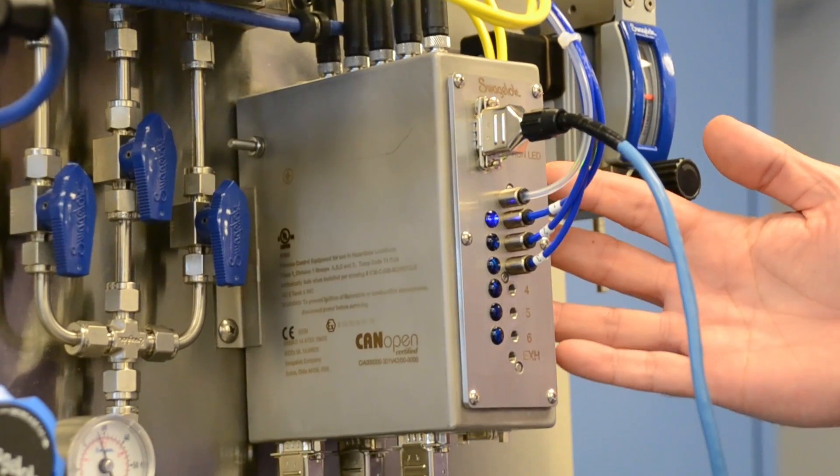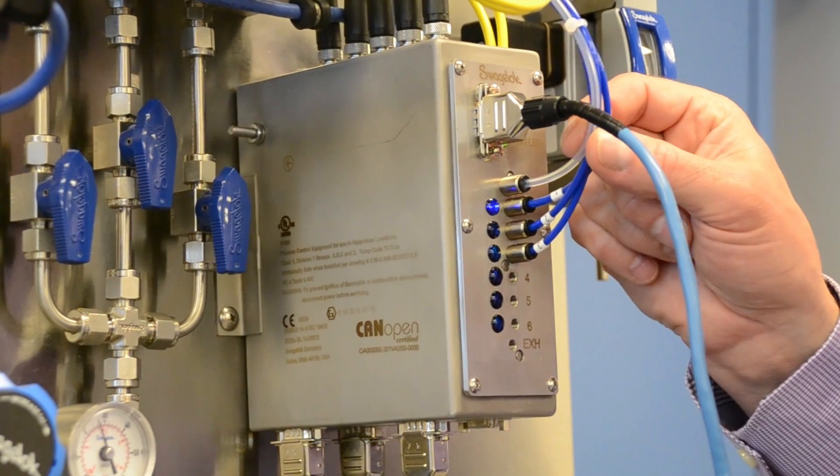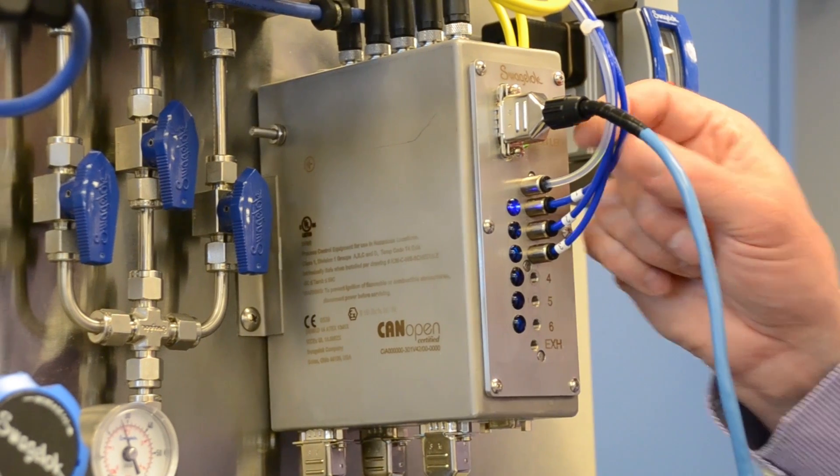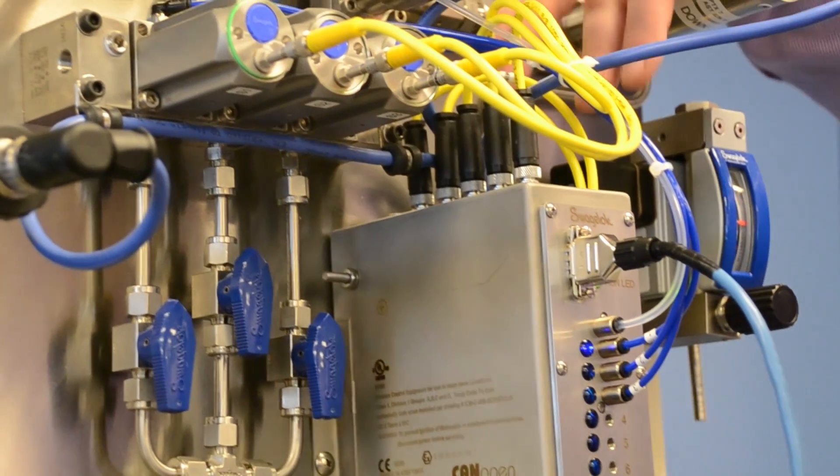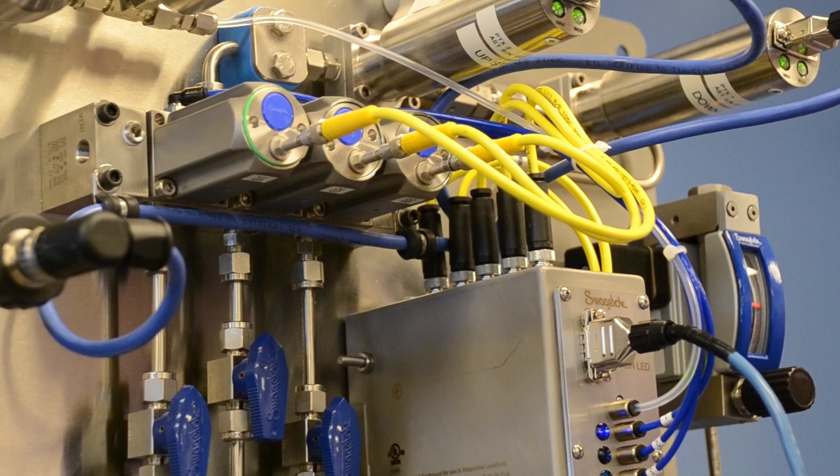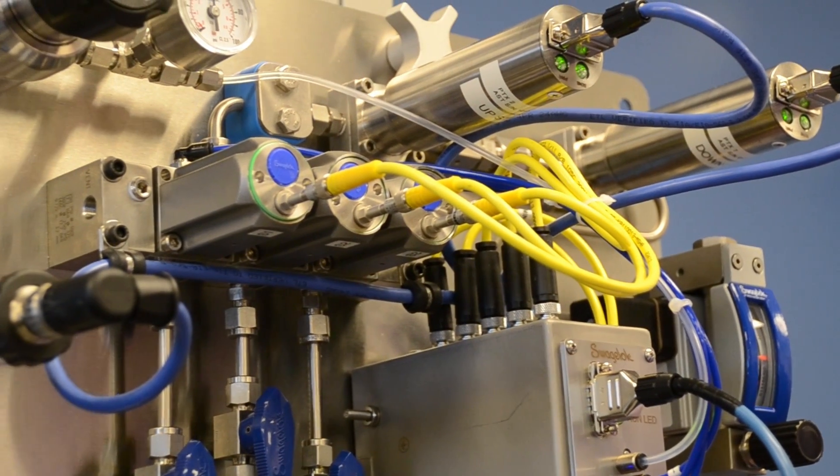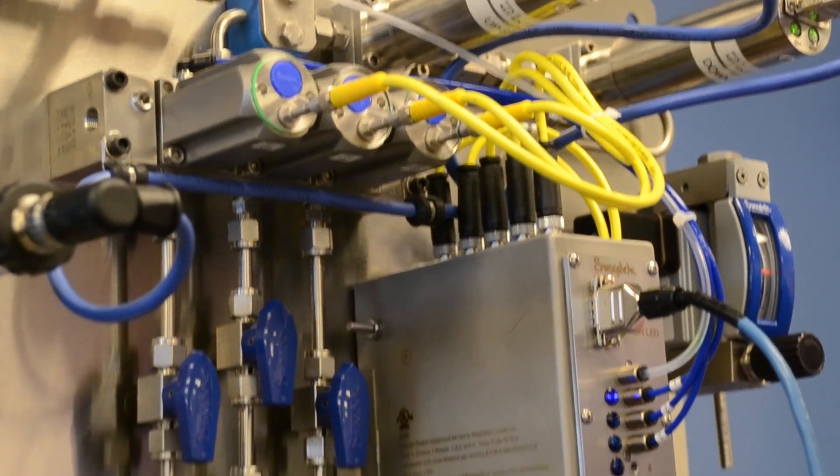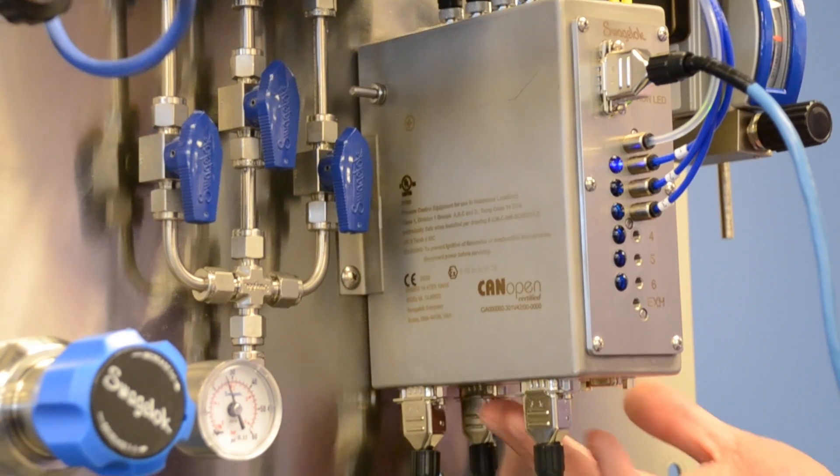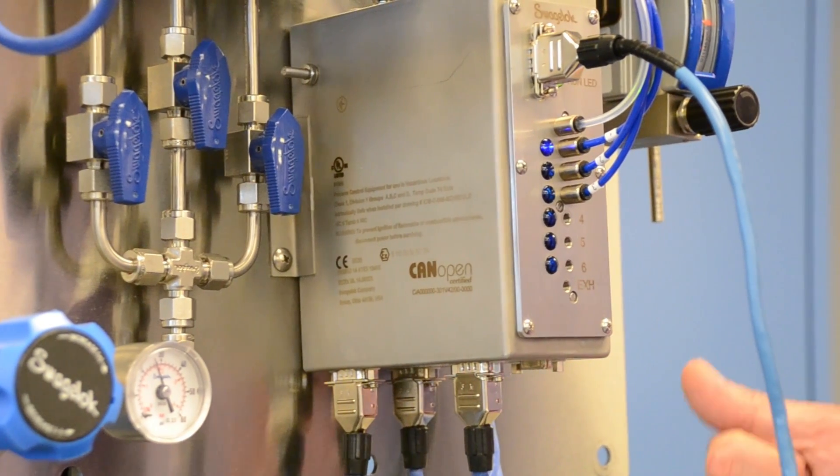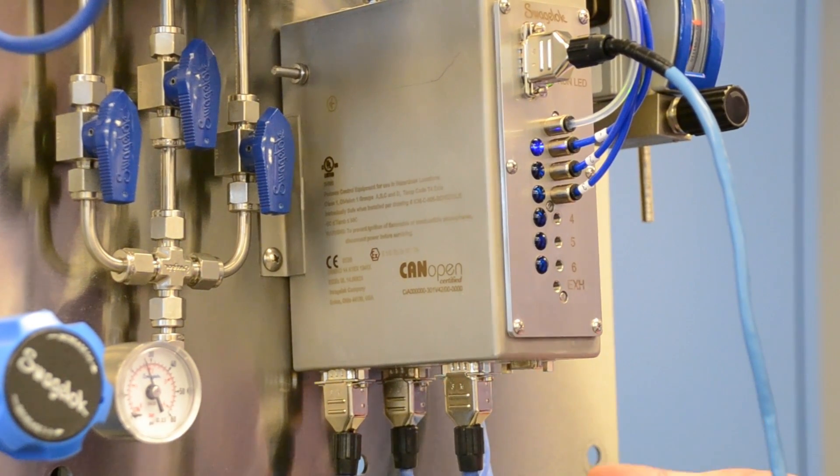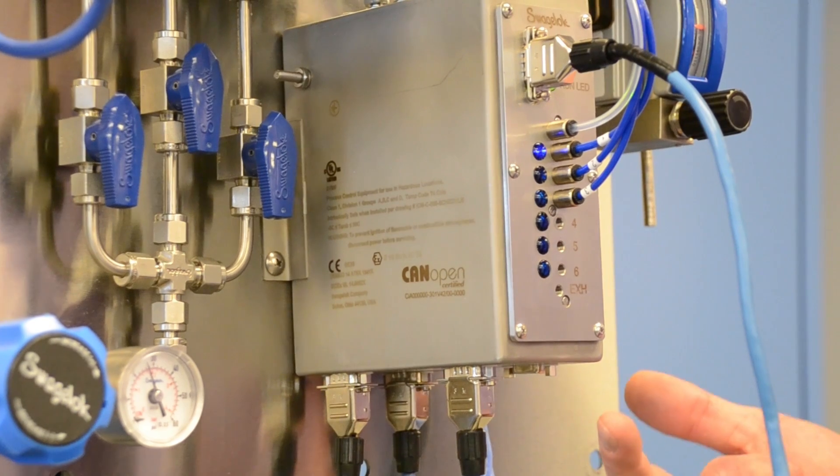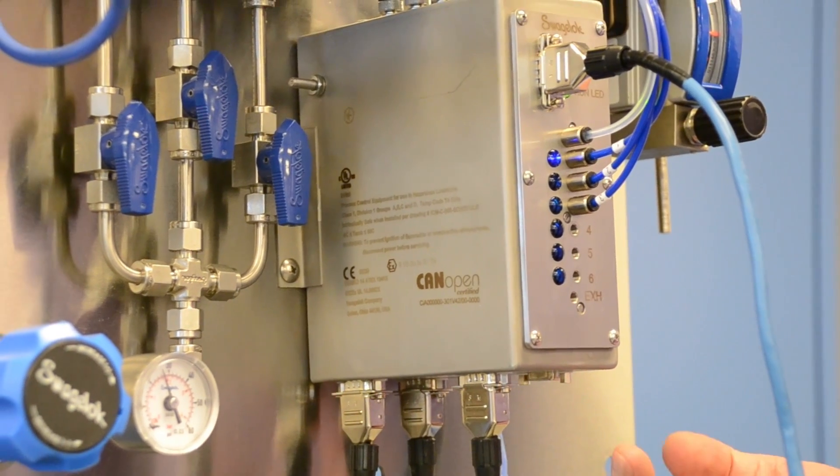So with an ICM, you can actuate valves with its pneumatic outputs, you can monitor digital inputs with its digital inputs, and you can monitor and power your sensors with its analog ports. There are four ports on the bottom of the ICM. Each port has both voltage inputs and a current input that make it versatile for use with a wide variety of sensors.